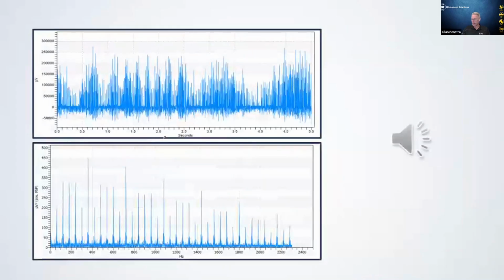Okay, and here again, it's the time waveform on the top, 5 seconds. And if we pull it down into the spectrum, now we see those 60 hertz peaks: 60, 120, 180, 240, etc. And so again, very indicative of corona discharge.